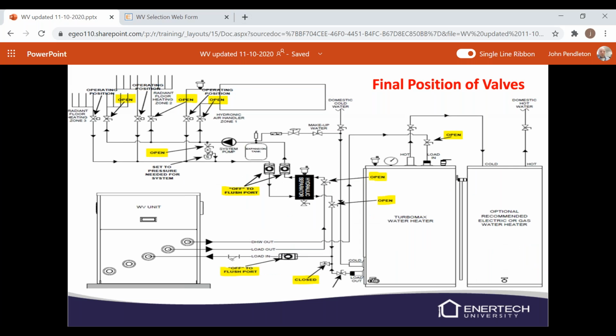Make sure you open up all your zones, all your ball valves, things like that need to be opened. Set your flush ports into the off position, and make sure all the other valves, your hydraulic separator, your buffer tank valves are open. Your domestic, your Turbomax tank valves are open. And if you've got a blowdown valve, make sure it's closed off. But these are just the normal positions of the valves once you're ready to operate the system.